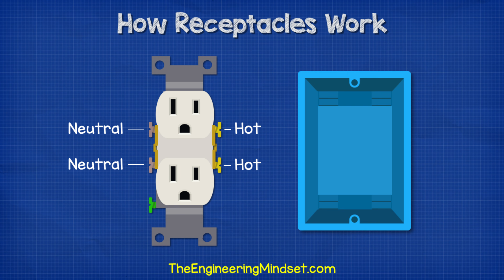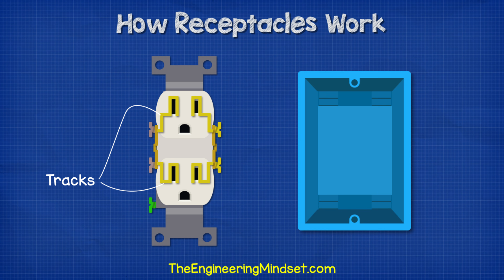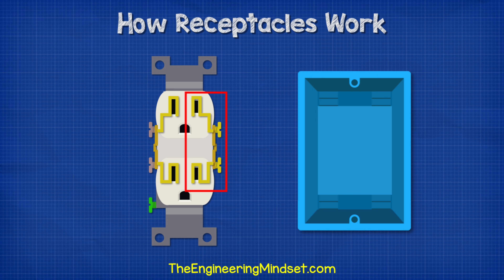So if we take a typical receptacle, we're going to find two neutral terminals on the left which are silver in color. And then there will be two brass colored hot terminals on the right. We'll also find a green ground terminal also. Between these respective sets of terminals, we have a jumper, but we're going to come back a little later in this video and look at that. Inside the outlet, we'll find some tracks which will carry the electricity. The two neutral and the two hot terminals are currently joined together by the jumper. So both hot terminals will become energized if either one of the two were wired into the circuit.